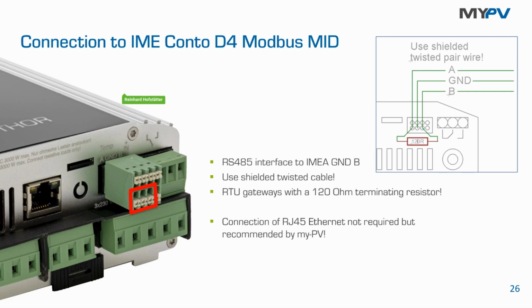One important detail: we recommend terminating the Modbus with a 120 ohm resistor. While this resistor is not included in the scope of supply of the Actor, it is included in the scope of supply of the AC Elwa 2. That's the difference. Please be aware. We recommend this resistor, and we also recommend using a shielded twisted pair cable. It should also be considered that the shield of the cable should be connected to earth, to ground, on one of both ends to have a stable communication with IME.